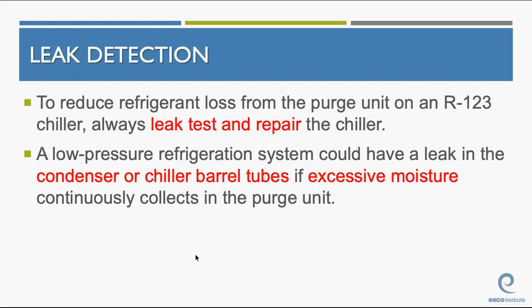Guys, again, water is going to leak from the chiller tubes, from the water side of the system, into the refrigerant if there's a leak in the condenser or chiller barrel tubes. The pressure of the water is actually higher than the pressure of the refrigerant. So the water is going to leak into the refrigerant, unlike the other systems that we talked about when we talked about water-cooled condensers, where the refrigerant will leak into the water. This way will be reversed because the refrigerant pressure is under the pressure of the water. Any questions on this?